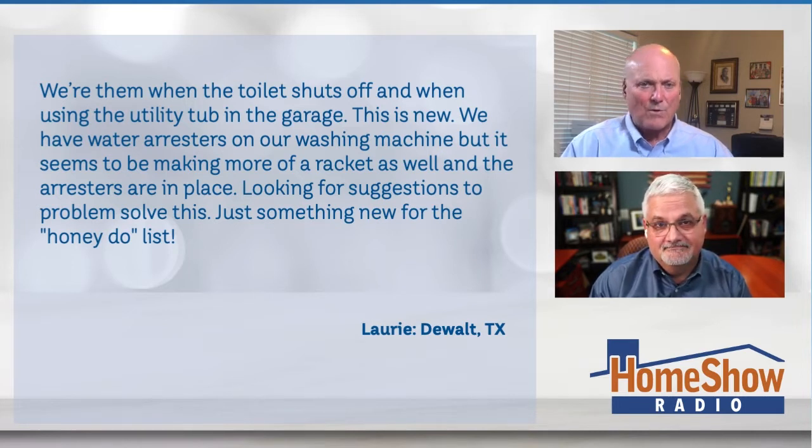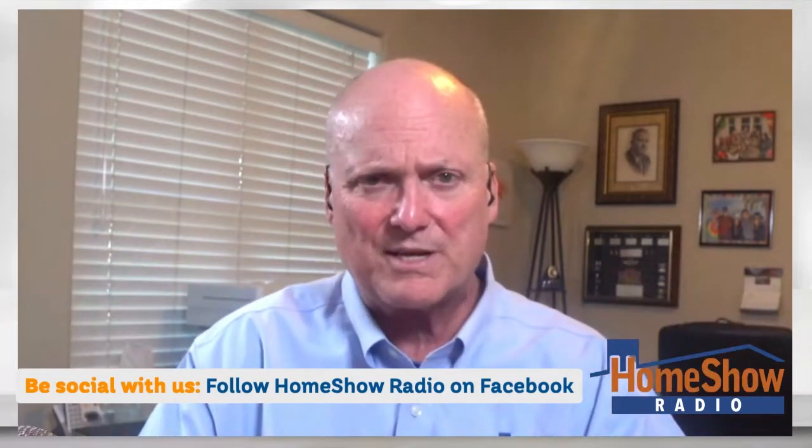Yeah, when you mention the toilets and everything, when it shuts off, it starts banging. The arresters don't do anything with that. In fact, quite frankly, I take them off because it does put some water restriction on there, and actually makes different kinds of noises, too. There's no reason for it to be on a washing machine. I don't know why anybody would recommend that, so I would get rid of that one. That's for hoses that are out and stuck in a flooded pond or something like that, that potentially could have water come back, but not in a washing machine. So get rid of those, and if that stops it, great.